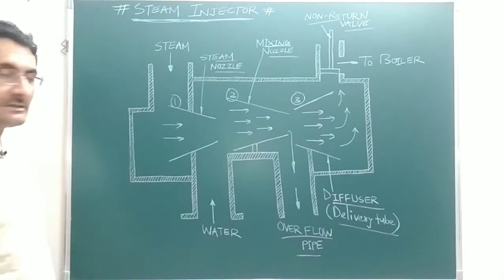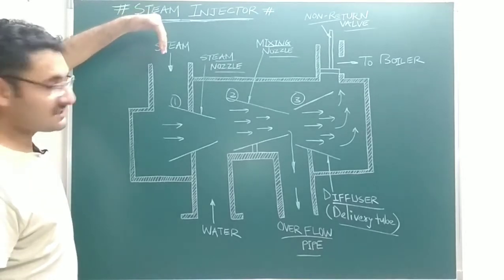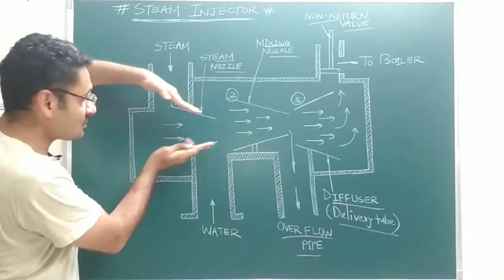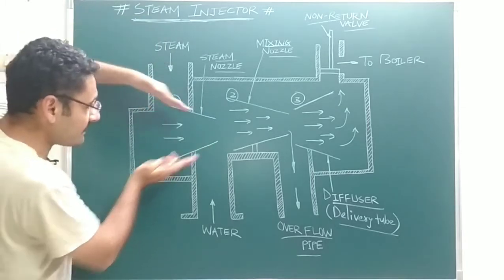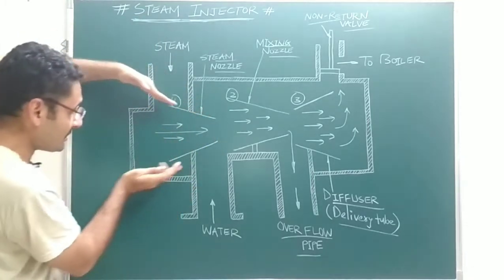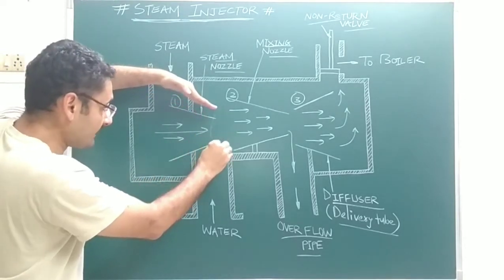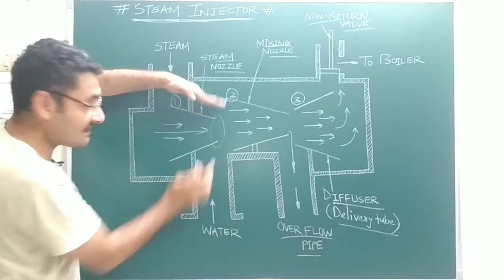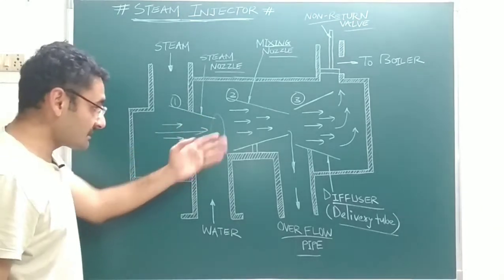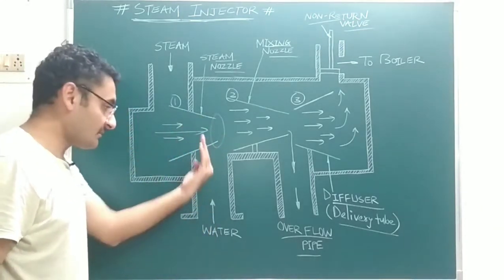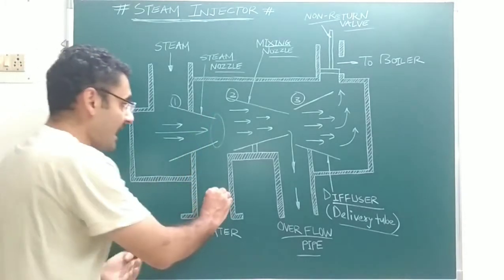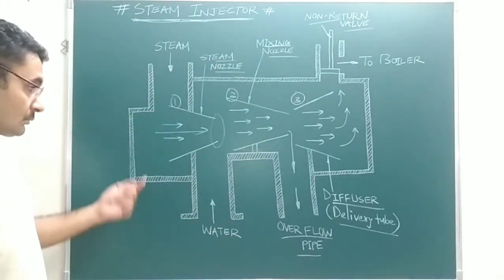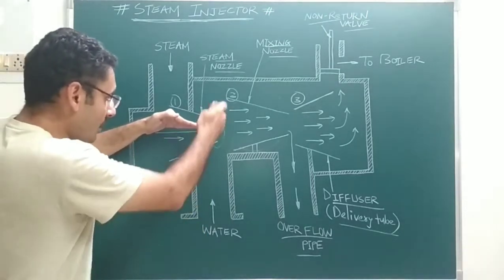In the working principle: steam enters from the first inlet into the steam nozzle. Inside the steam nozzle, the velocity of the steam is increased, and at the outlet of the steam nozzle, pressure drops — pressure is decreased. Due to this, a suction effect is produced, and water is drawn upward to mix with the steam in the mixing nozzle.